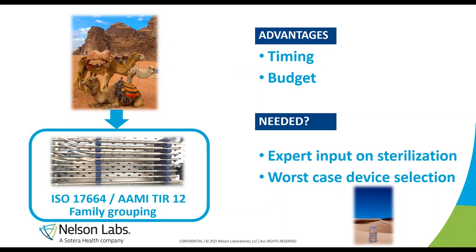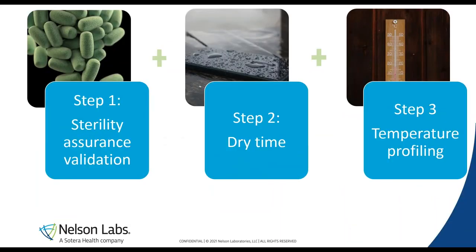The worst-case device selection is very important — that's where you can save time and money. Once you have done that, you can proceed to the validation of your process, which consists of three individual steps: Step 1 — sterility assurance validation; Step 2 — dry time; and Step 3 — temperature profiling.